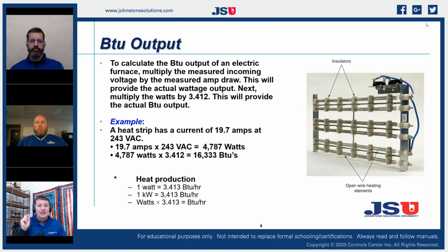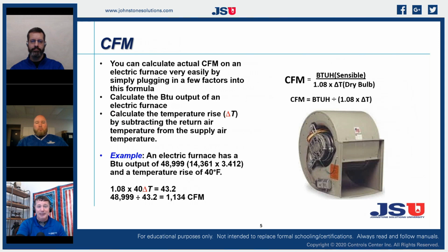So if I take my watts times 3.412, that is my actual BTUs that's being generated by this furnace. If I was doing a heat load calculation on a house, this is exactly what I would do to size my elements. As I look at my BTUs that's being produced by it. We always think of BTUs on a gas furnace. We never think about BTUs on an electric furnace, right? Well, it's pretty simple. That's our watts times 3.412, and that is BTUs. Now we've got something really cool to work with. If we take our BTUs, so let's assume I have a 15 kW heater.